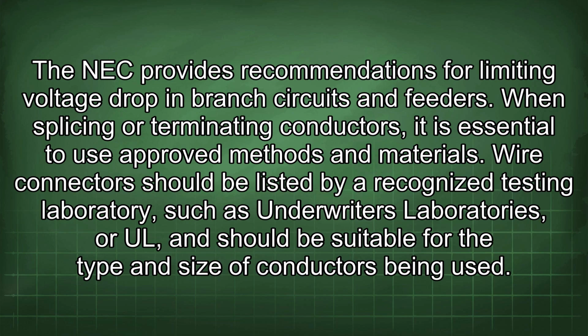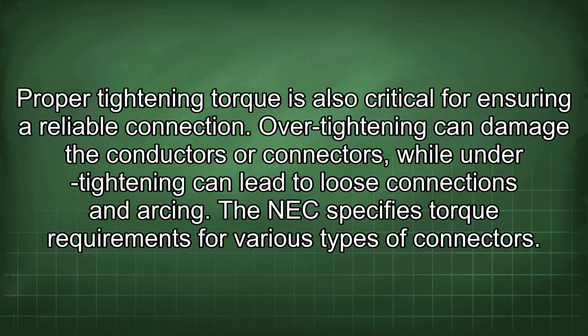When splicing or terminating conductors, it is essential to use approved methods and materials. Wire connectors should be listed by a recognized testing laboratory such as Underwriters Laboratories, or UL, and should be suitable for the type and size of conductors being used. Proper tightening torque is also critical for ensuring a reliable connection. Over-tightening can damage the conductors or connectors, while under-tightening can lead to loose connections and arcing. The NEC specifies torque requirements for various types of connectors.